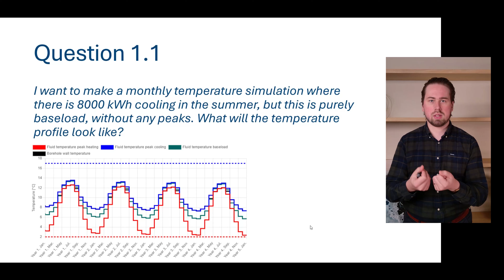And the temperatures during cooling, during heat injection, are the theoretical minimum temperatures. Basically, if we need to inject a certain amount of heat into the ground in each month, there is a minimum power required for it, so that if we have 100% of this power during the month, 730 hours long, we will end up with this profile. So our fluid temperatures during peak cooling will overlap with our baseload temperatures. Our profile would look something like this, where you see that in summer our green line for the baseload temperatures overlaps with our fluid temperatures during peak cooling. Because when we assume there is no peak power for cooling, we just end up with the baseload power that is required in order to deliver the energy.